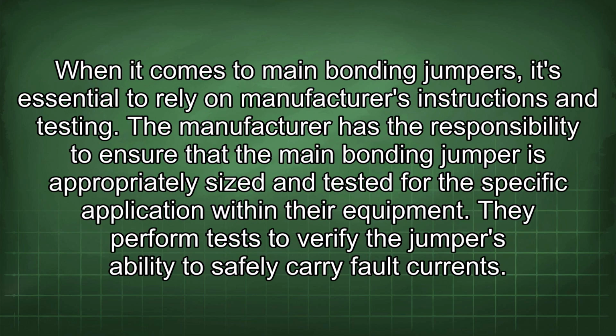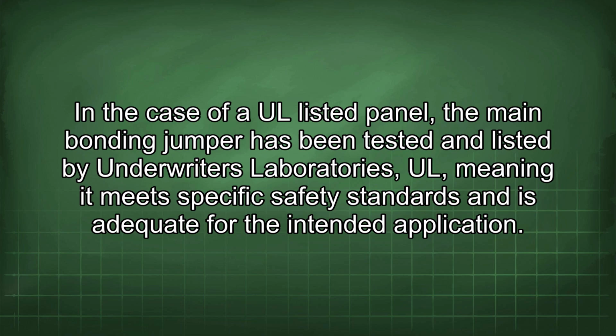Thirdly, corrosion on the screw or the connected surfaces can also increase resistance and reduce ampacity. When it comes to main bonding jumpers, it's essential to rely on manufacturer's instructions and testing. The manufacturer has the responsibility to ensure that the main bonding jumper is appropriately sized and tested for the specific application within their equipment. They perform tests to verify the jumper's ability to safely carry fault currents. In the case of a UL-listed panel, the main bonding jumper has been tested and listed by Underwriters Laboratories, meaning it meets specific safety standards and is adequate for the intended application.